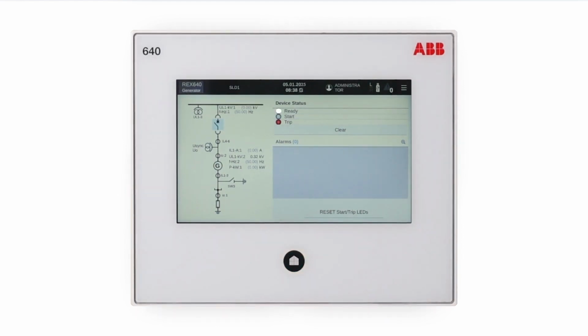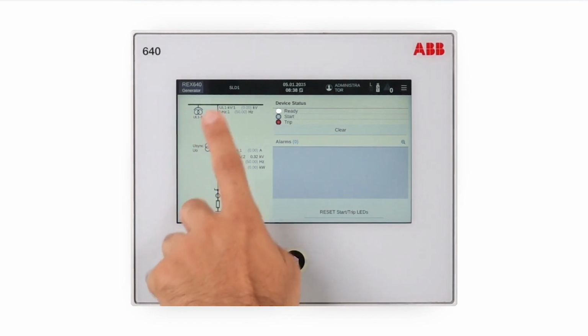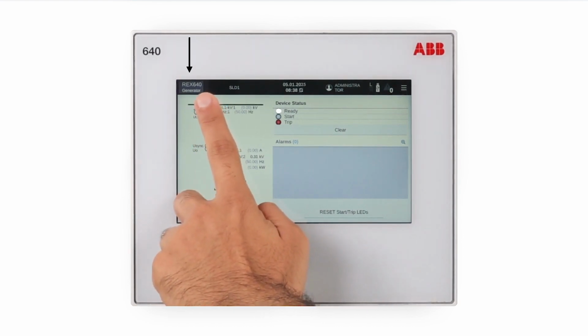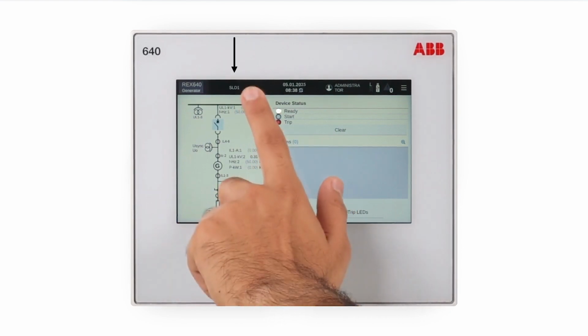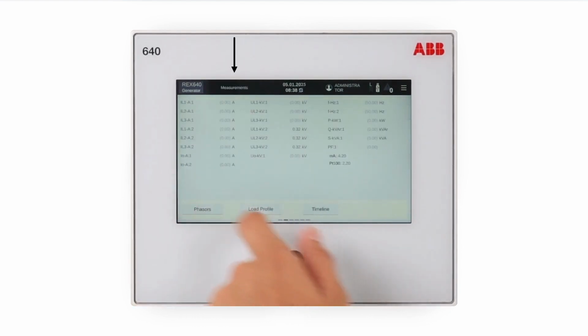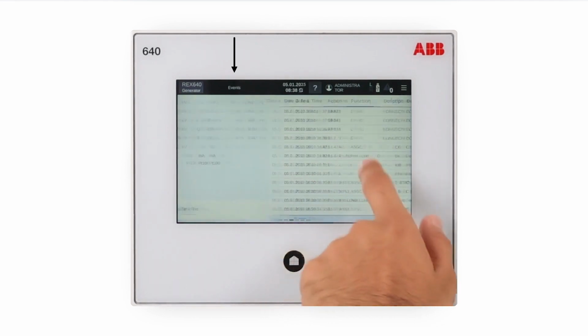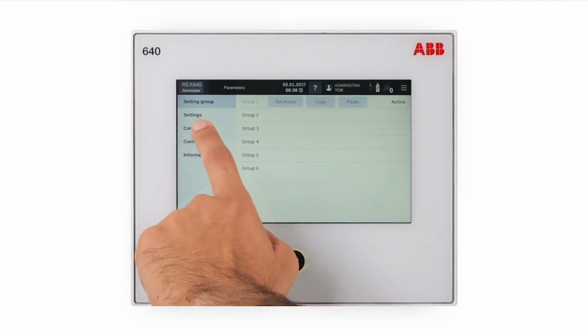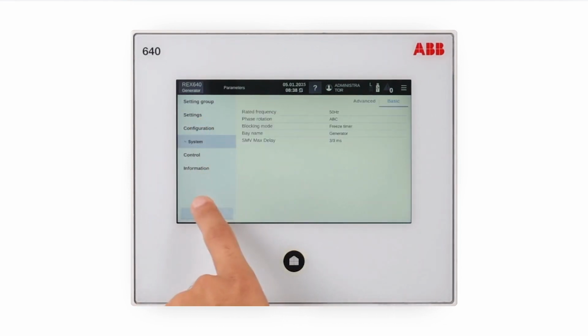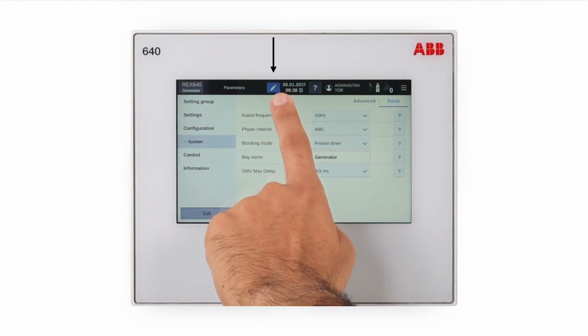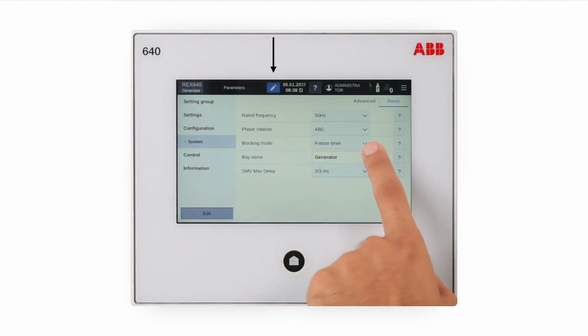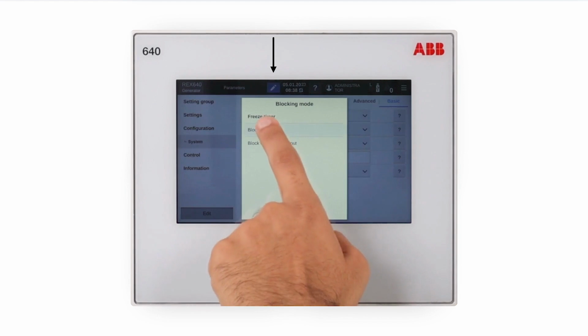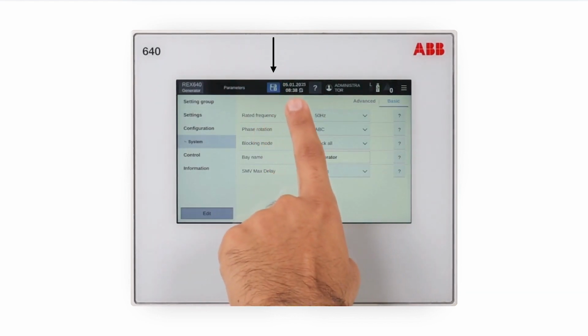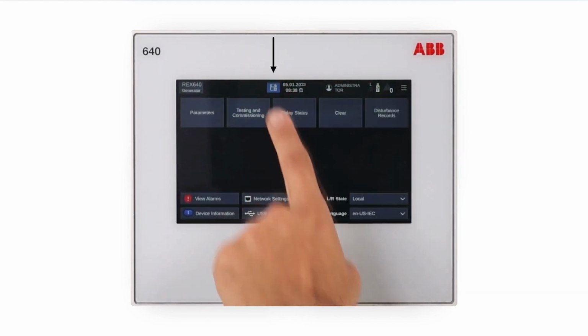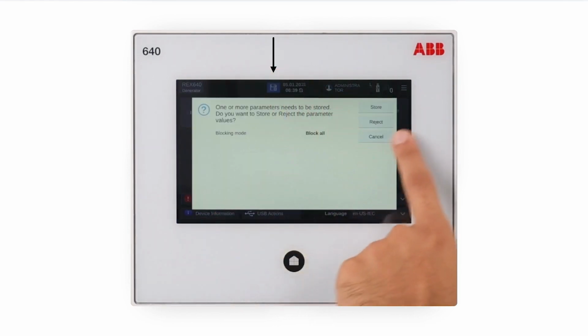The menu bar contains multiple indications and options for quick access. The bay name for the relay is indicated on the top left corner of the LHMI. To its right, the page name is indicated. This will display the name of the page currently open. Edit mode active or parameter editing icon will appear when you are editing parameters. Subsequently, once you make changes, this icon will be changed to store or reject changed parameters indication. By clicking this, you can commit to the changes or reject it.